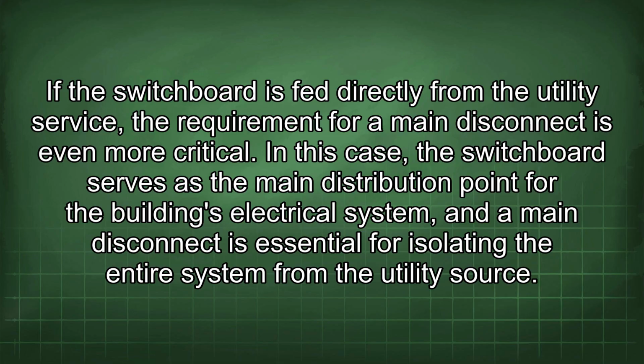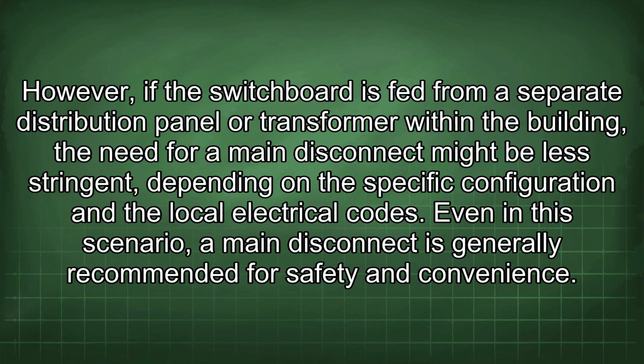In this case, the switchboard serves as the main distribution point for the building's electrical system, and a main disconnect is essential for isolating the entire system from the utility source. However, if the switchboard is fed from a separate distribution panel or transformer within the building, the need for a main disconnect might be less stringent depending on the specific configuration and the local electrical codes. Even in this scenario, a main disconnect is generally recommended for safety and convenience.